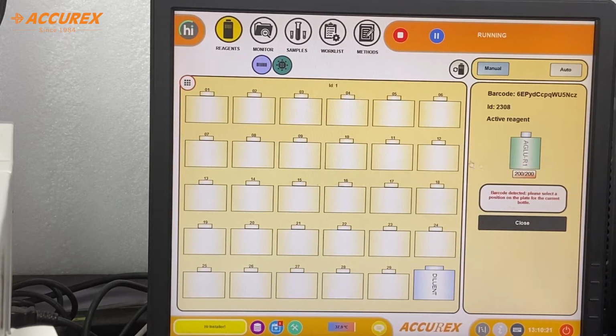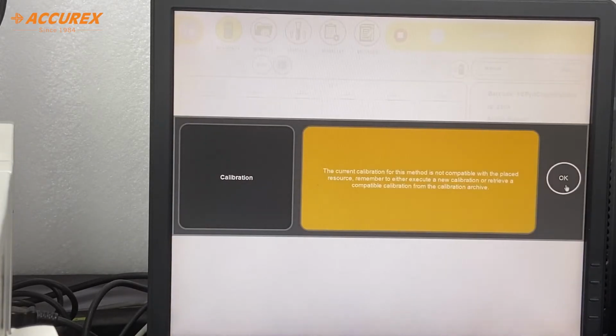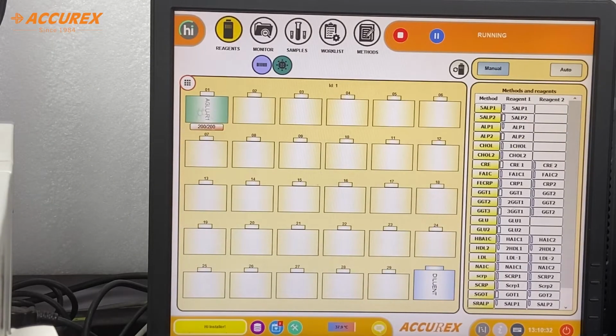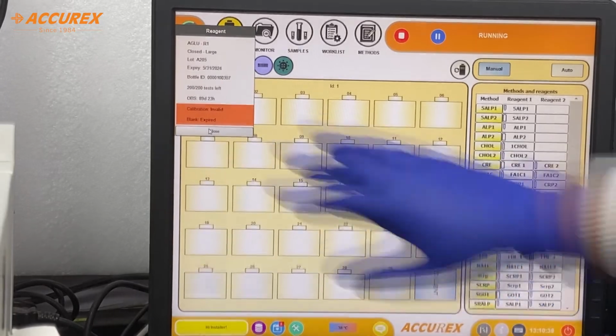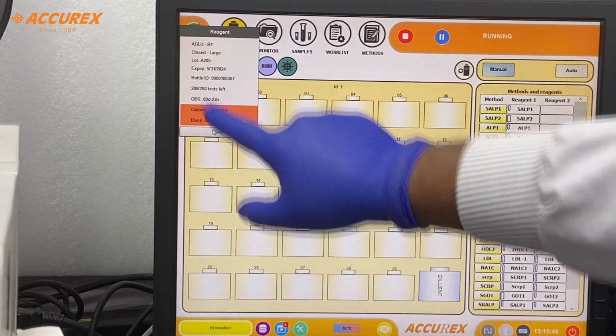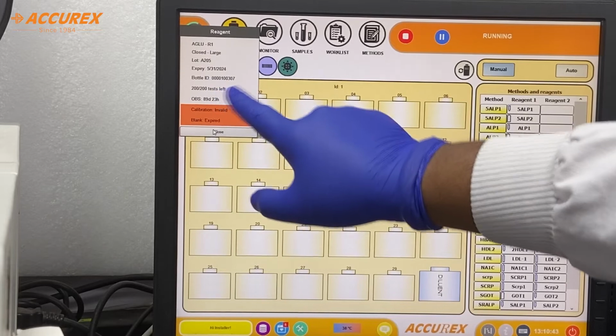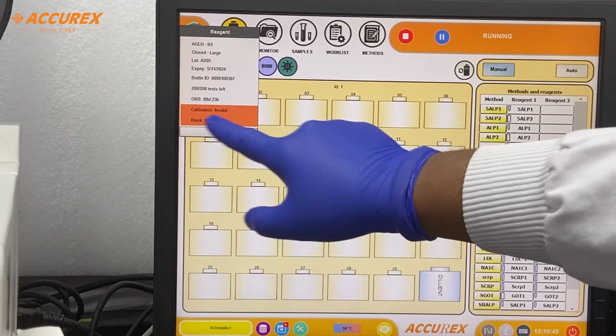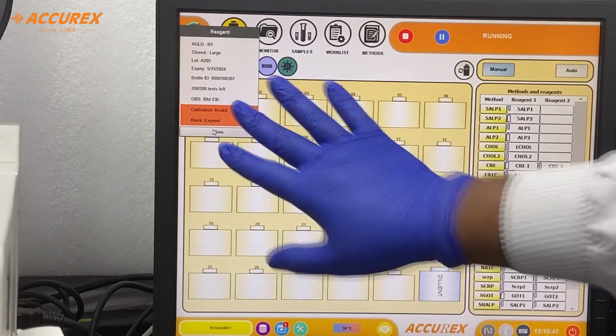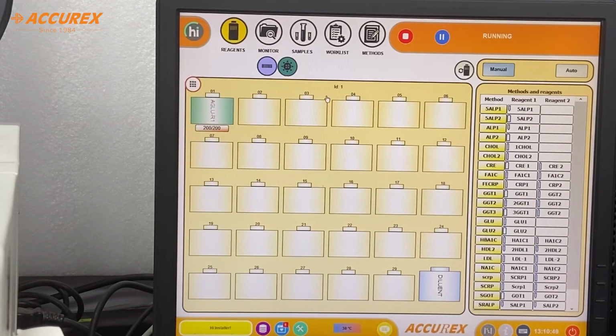Click on the bottle, and then click on the screen where you need to assign the reagent bottle. Click on the reagent bottle and click on the position. After clicking on the position, it will show the screen over here with the number of tests. Since we need to do the calibration, everything is in red color. You can see all the description while clicking: the large bottle, pack size, bottle ID, OBS expiry, calibration valid or invalid, everything is mentioned over here. Okay, so after that, we need to do the same thing with the other reagents also.